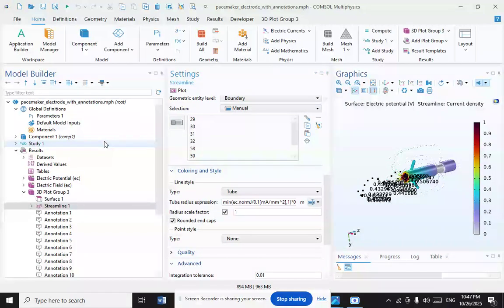For some pacing leads, both connections to the heart are provided in a single lead, bipolar, and some only provide a single connection, unipolar. In unipolar, the second connection is internally from the heart to the generator through the body, blood, tissue, etc. Also important is the impedance. The lower the impedance, the more current is needed to achieve the threshold voltage and it lowers the battery life. The impedance is affected by the integrity of the pacing lead and the electric tissue interface of the lead with the heart. And the next is sensing and sensitivity.